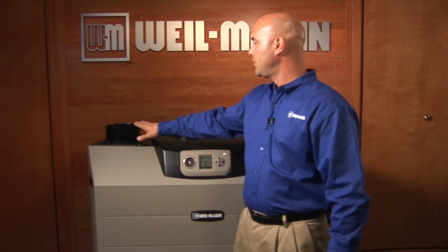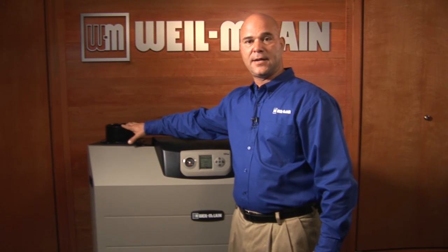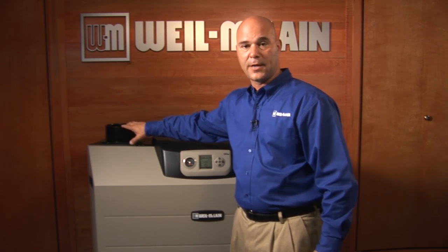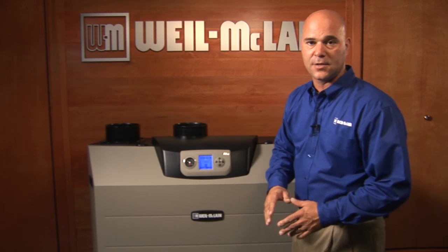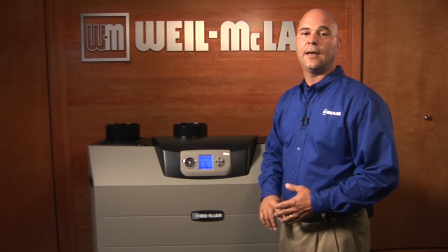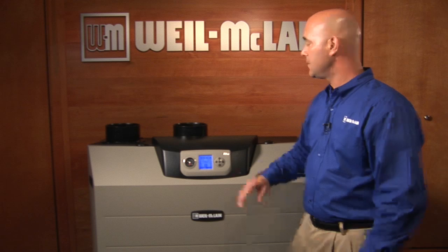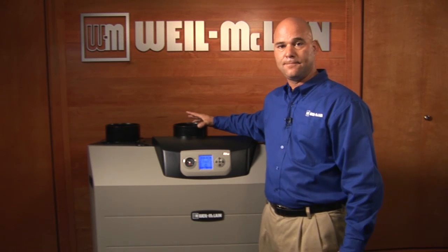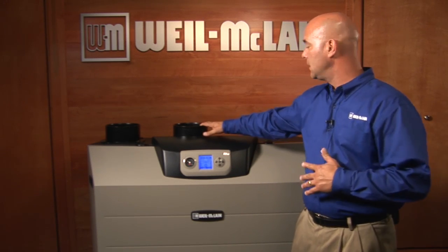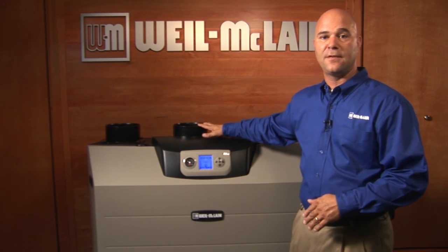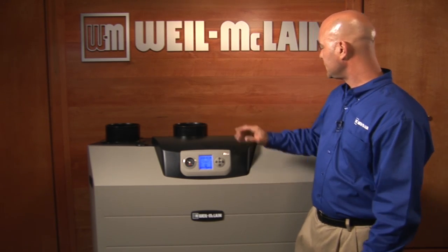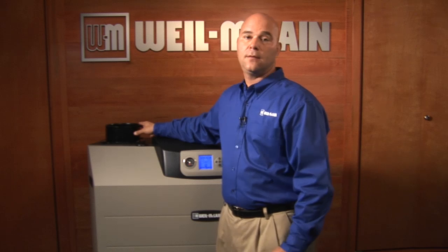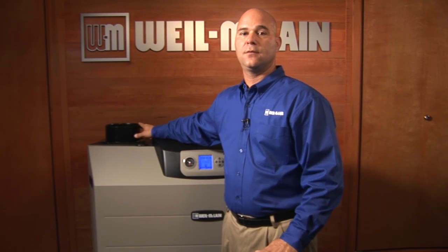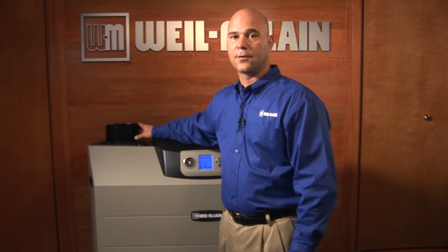As far as the top of the boiler goes, on the left side, this is the 6-inch termination. It's going to be a 6-inch termination on both the 550,000 and the 750,000 BTU boiler. There's also a fresh air inlet. This fresh air inlet is also 6-inch on both the 550 and the 750. It can be vented either sealed combustion or direct exhaust, either or.